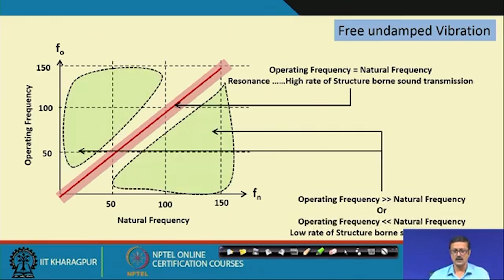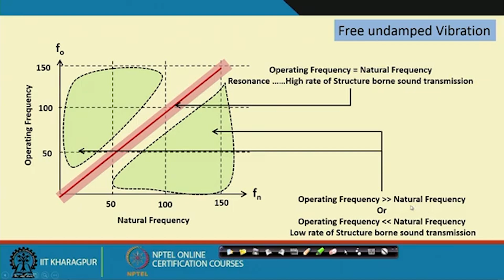So, that is why I have drawn a 45-degree line, the red line, where f o and f n match together, and this red zone is the zone where the operating frequency almost matches the natural frequency, resonance is created, and a high rate of structure-borne sound transmission will occur. So, our idea is that the combination of operating frequency and natural frequency should come in this green zone, either below or above. Then resonance will not occur, and if the natural frequency is high or low relative to the operating frequency, a low rate of structure-borne sound will be transmitted.